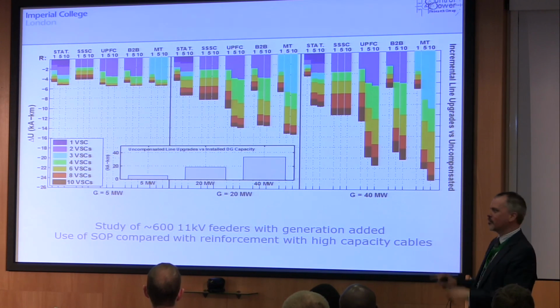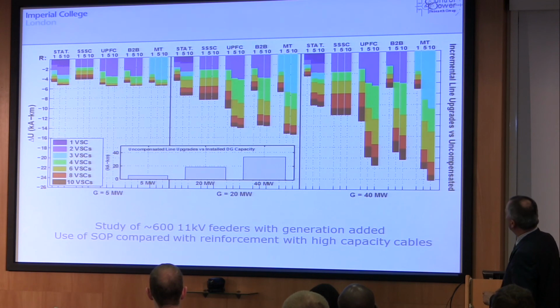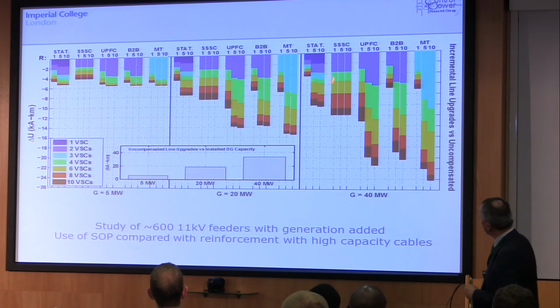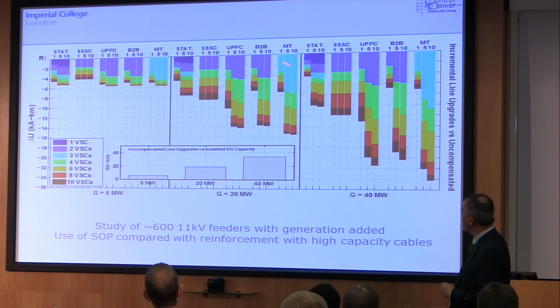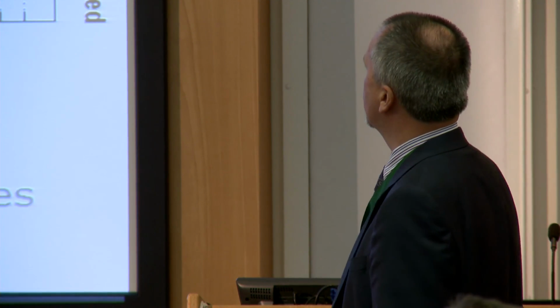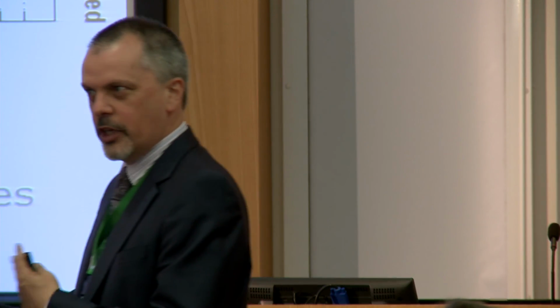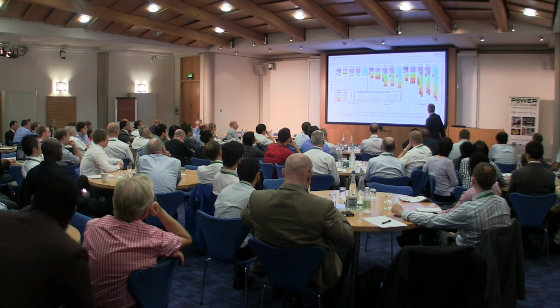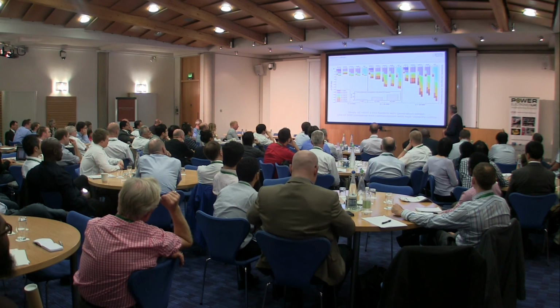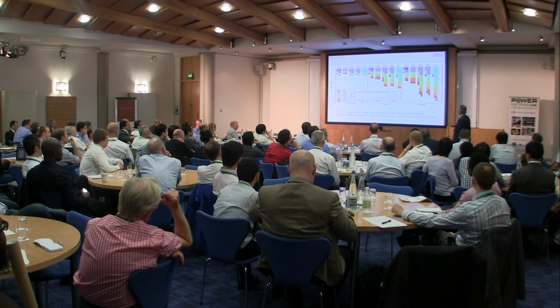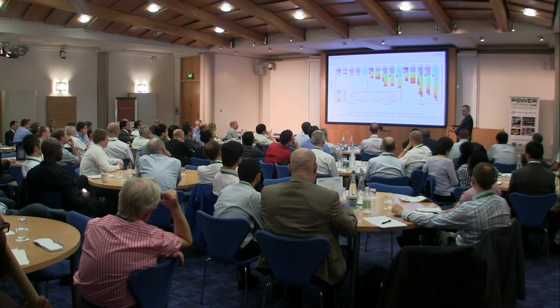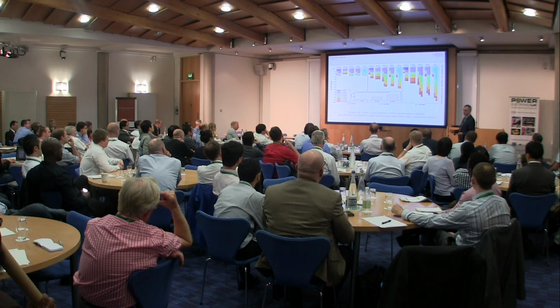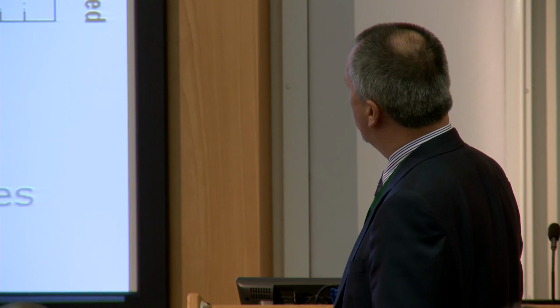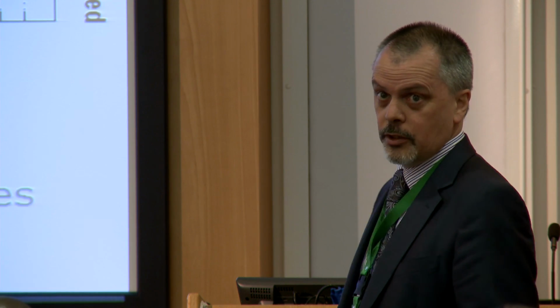Somewhat busy slide that I pulled from a paper, but the point was that actually at 11 kV, and that's where this study was, you can do quite a lot with a StatCom, but the other converters are more effective. The series converter is a bit more effective, but the series converter is also really only a reactive power device, so it struggles. The UPFC, which can do real and reactive manipulation, is effective. It only processes a fraction of the transfer power, which is nice, and therefore it generally beats the back-to-back converter.